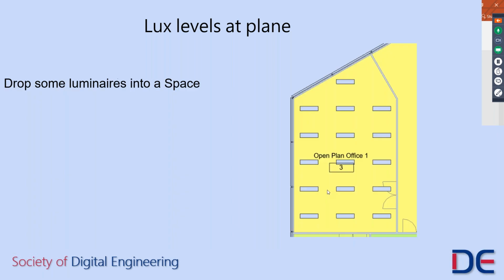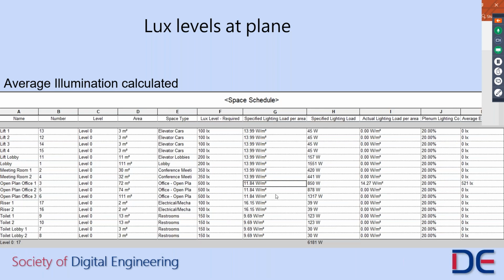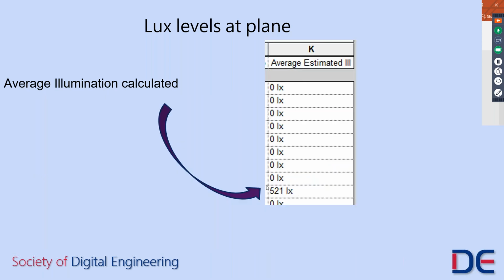So let's do that. Let's put some luminaires into a space. Here's one of the spaces that we looked at earlier, and I've just dotted in some luminaires for demonstration purposes. Now we can see that we have some values within the actual lighting load and the average estimated illumination. As we can see here, it's come very close to the 500 lux that we required.